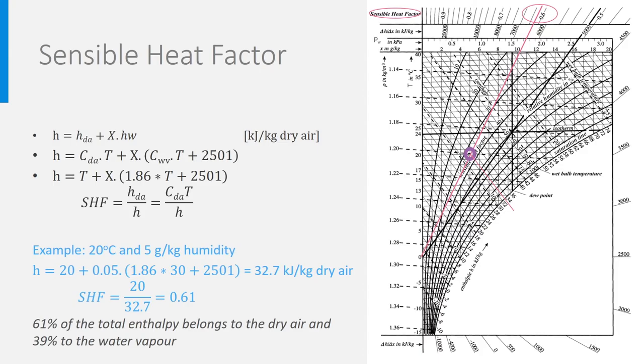We will not use this factor further. If we look at the process in the psychrometric chart, we see that heating at constant absolute humidity goes to the right and the enthalpies can be read here. So, you see some small differences in the absolute values when compared to the Mollier diagram, but this has to do with the precision of the graphics and the goodness of your eyes. The enthalpy difference is identical.